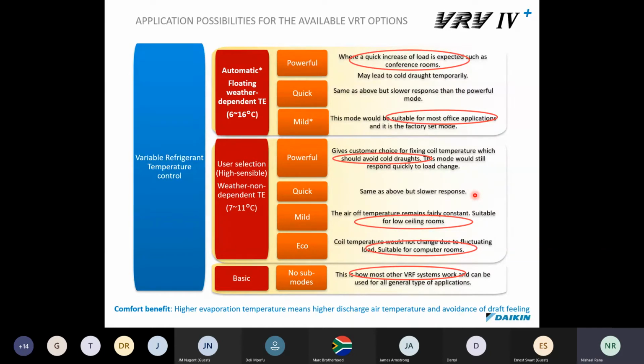So as I explained earlier, let's say, for example, the customers have an office full of people who prefer it to be warmer, but they still want to eliminate the humidity. You could change your evaporation temperature from 6 degrees to possibly 9 degrees, if that's what suits them. The fact of the matter is that the flexibility is there.